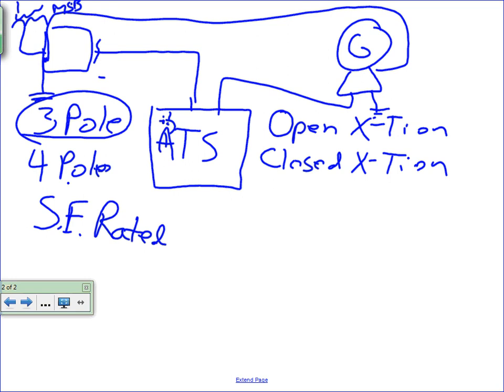It really depends on the ampacity of it, but it's probably 15%, 20% more. As you get into the bigger ones, it gets much larger than that, but in the smaller ones, it's not as big a percentage change. About the difference in price between the both, that is probably a significant change, right? Because on a closed transition, we need a sync check relay where we're feeding voltage from both sources, and the relay itself is checking when they come into sync, and at that point it'll start doing the transfer. It requires more control and more protective relays and stuff like that. So it is more expensive.